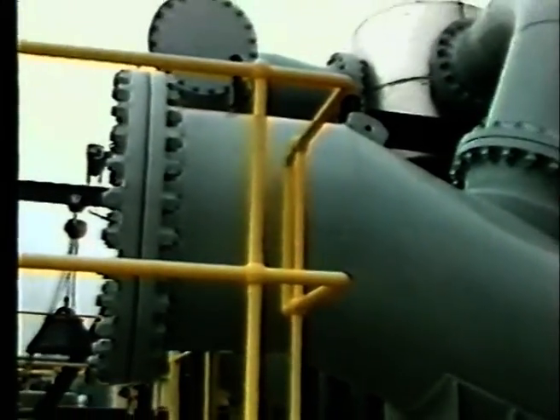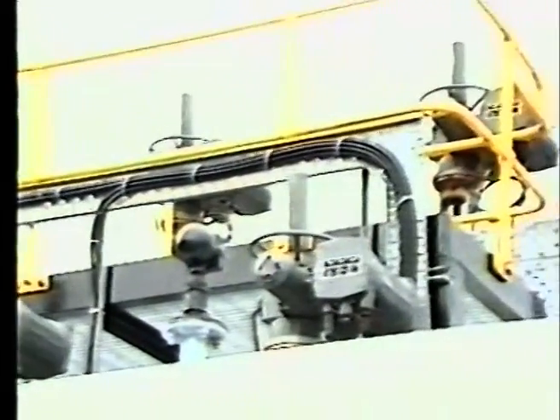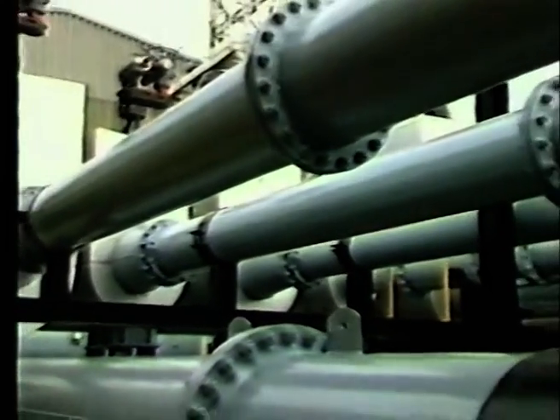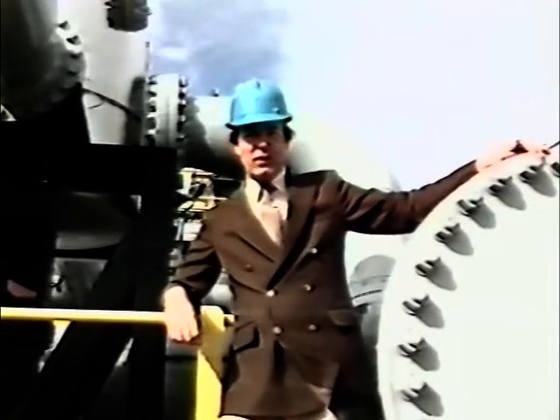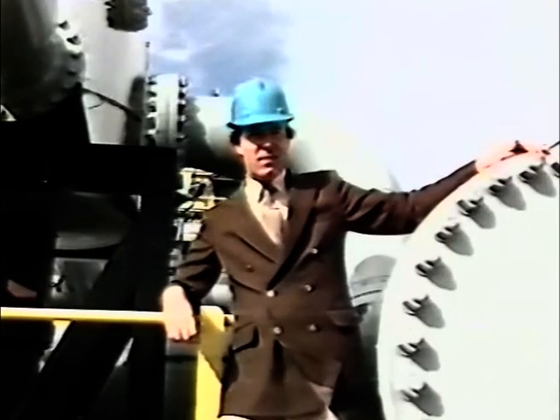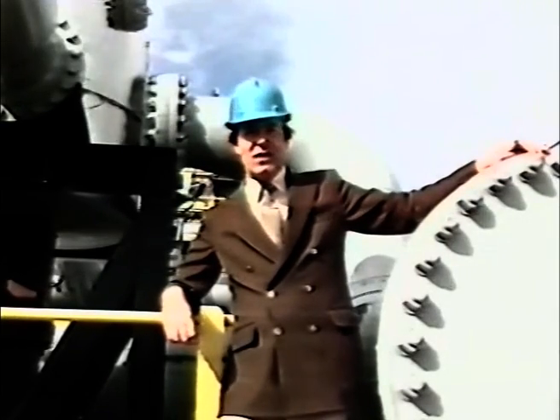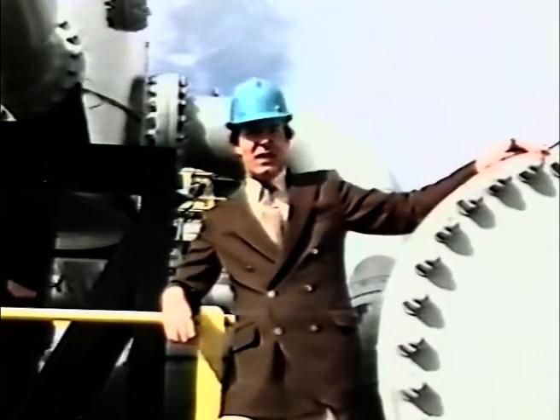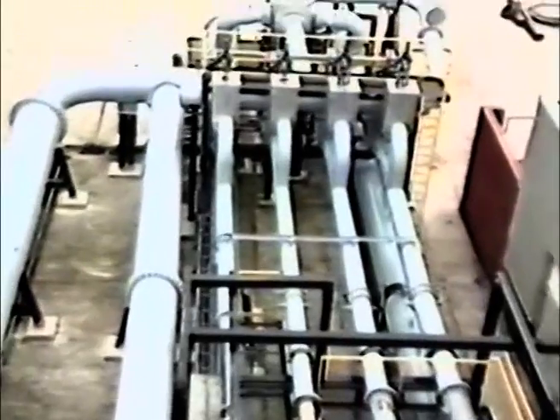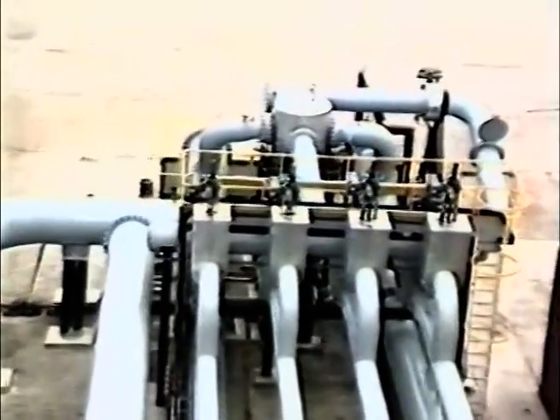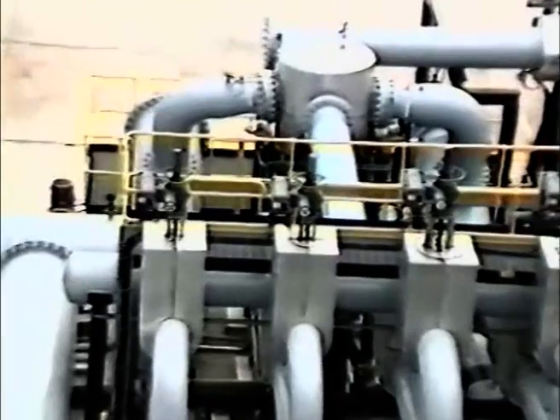A variety of other test rigs can handle meters as small as 3 millimeters in diameter, with flow rates as low as 12 litres per hour, and further enhancements are well underway, which will maintain the plant's leadership performance well into the next decade. It all underpins the importance the Brown Boveri Kent Group place on their customers in the oil, water, power and process industries. Many customers outside the group make extensive use of this facility, which is the only UK or European facility able to operate continuous flow testing at rates of up to 10,000 cubic metres per hour.